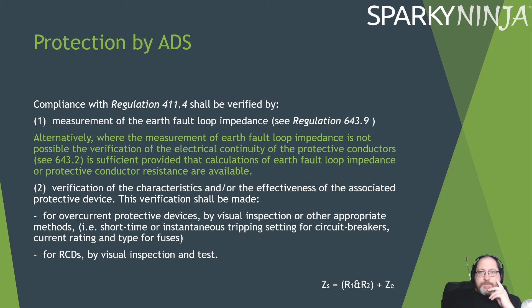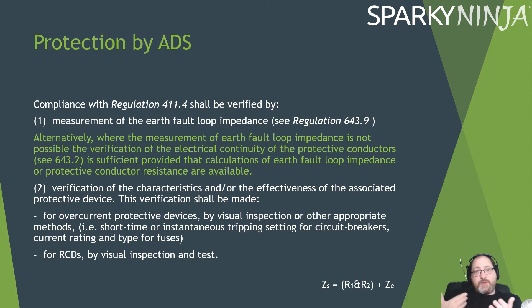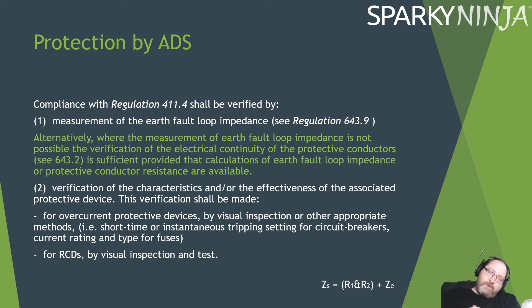Protection by ADS: compliance with Regulation 411.4 should be verified by measurement of the earth fault loop. Alternatively, when the measurement of earth fault loop impedance is not possible, verification of the electrical continuity of the protective conductors is sufficient, provided calculations of earth fault loop impedance or protective conductor resistance are available. So this is saying you can verify earth fault loop impedance if you have a measurement of continuity of the protective conductor — ZS equals R1 plus R2 plus ZE — confirming we can verify earth fault loop by a confirmed continuity measurement.